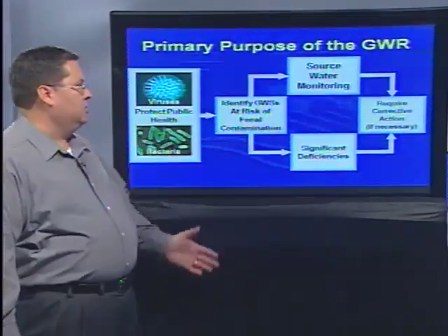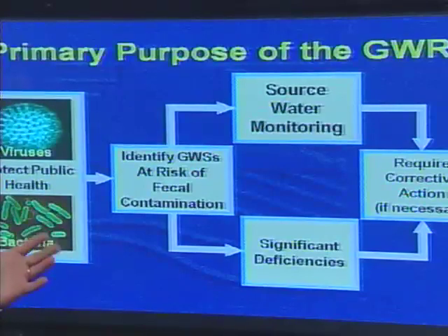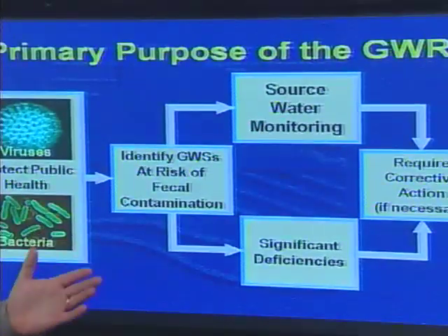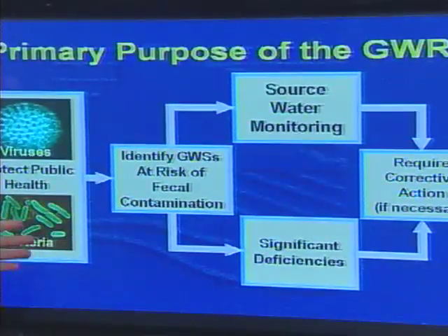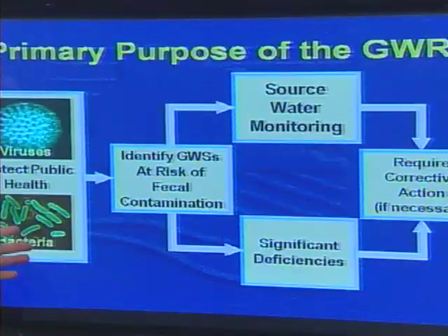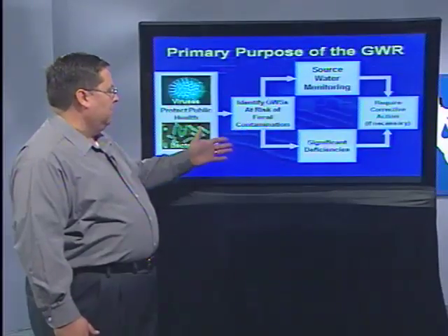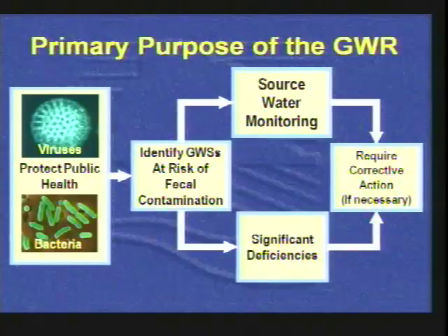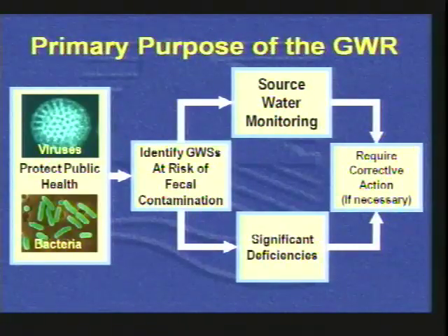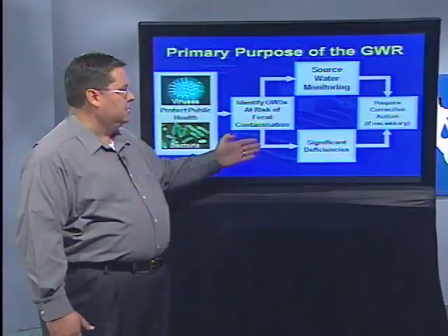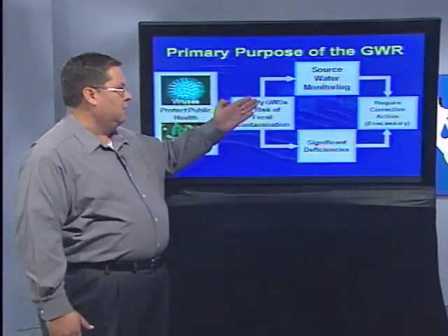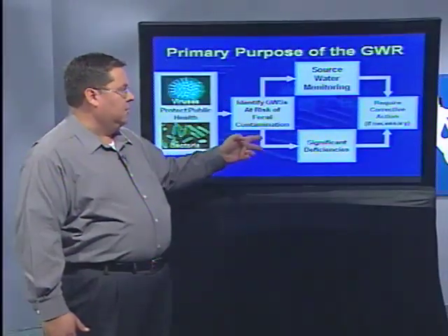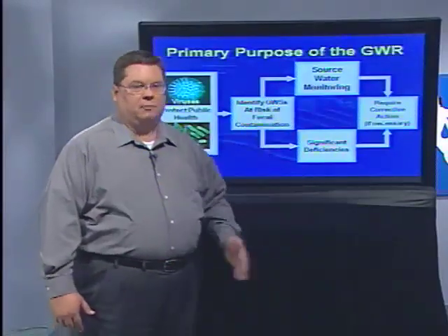Here we have an illustration of the overall purpose of the Groundwater Rule. It does provide increased protection against microbial pathogens. Some of the processes involved are that we identify groundwater sources that are at risk of fecal contamination through sanitary surveys. Those sanitary surveys could discover significant deficiencies. Along with that we have source water monitoring, and if things are discovered then we would require corrective action.